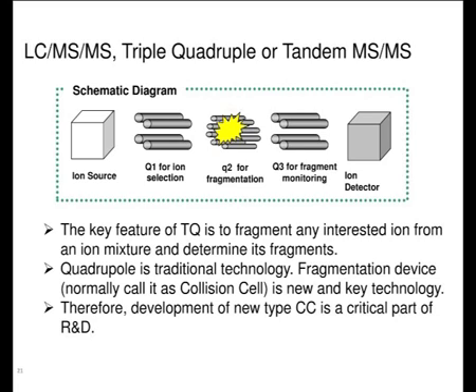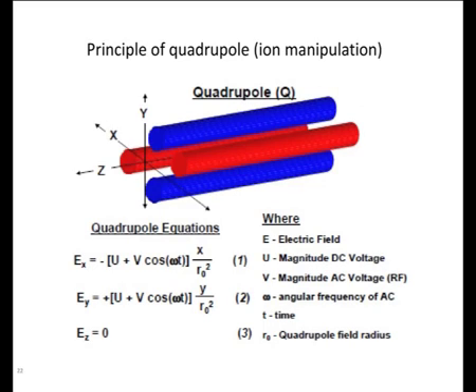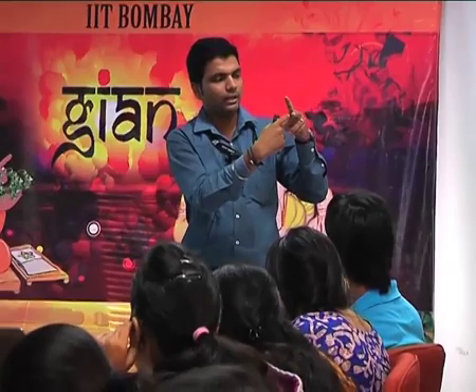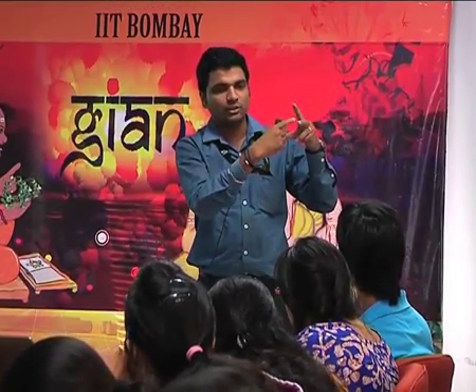The quadrupole, we already discussed its principle. It contains four molybdenum rods, and the opposite rods have similar charges. You are providing RF and DC voltage, but that voltage is not constant, it fluctuates. When the ions are introduced into the quadrupole, for example, if an ion has a negative charge, it is attracted toward the positive rod, but when it goes toward that rod, the charge gets changed to the next rod, so the ion moves to the next rod, and when it is about to reach that rod, the charge changes again.